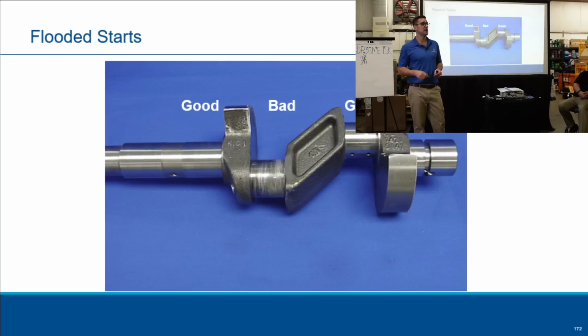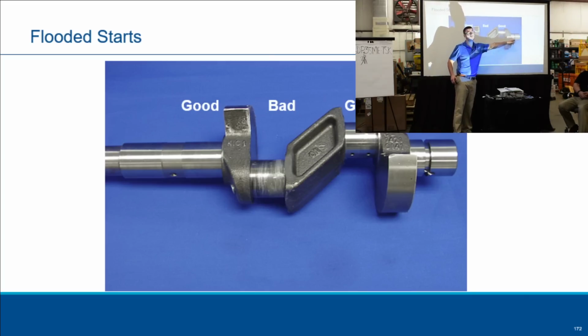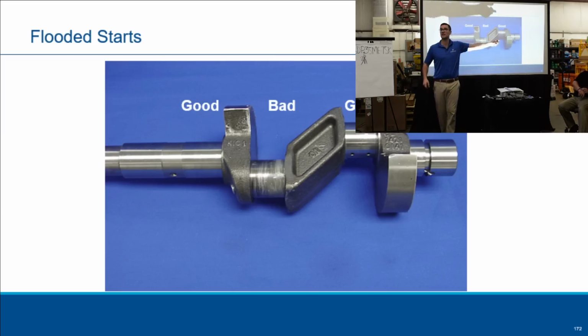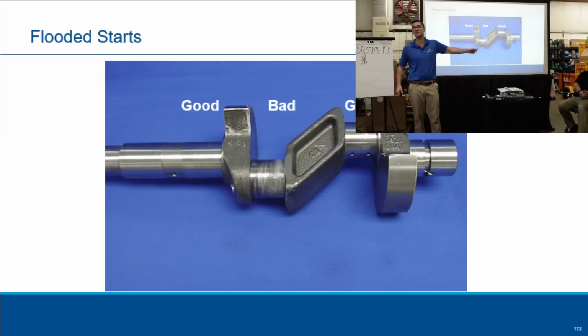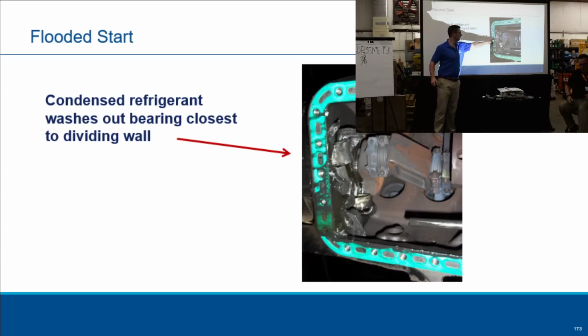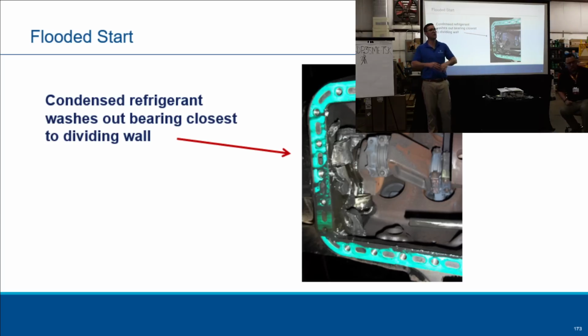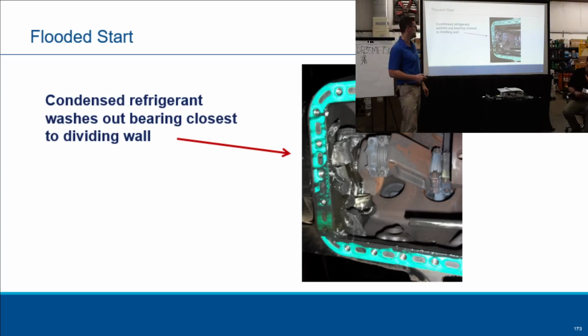And it was, the liquid refrigerant hit there first. This is where the first oil should be getting, right at your oil pump. If it seizes on there, that's the flooded start. Or here. So that refrigerant gets up there, explodes and washes all the oil out, and then you don't have that lubrication.